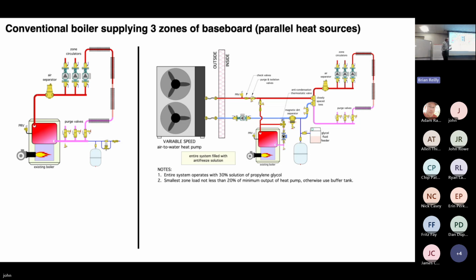So if you look at what's going on here, the heat pump and the boiler are piped in parallel. In other words, the common fluid returning could go into the boiler, or it could go into the heat pump, or it could do both at the same time. So the boilers are in parallel with each other. There is a check valve in each of the circulators, so we don't get reverse flow. I also put purging valves on each one of them, and this would be an isolation flange.